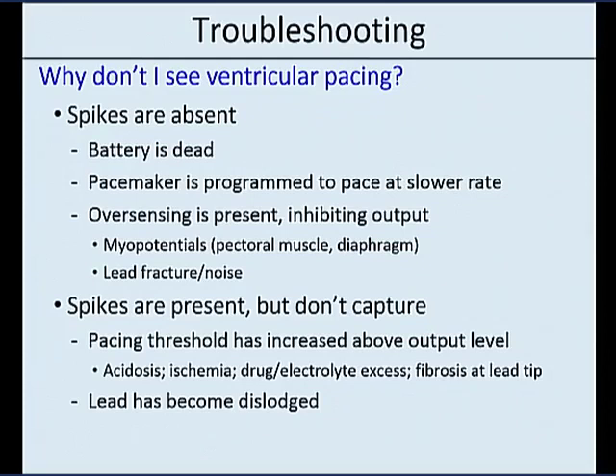Or the pacemaker is programmed to go at a slower rate than the prevailing rate. And if you say, hey, the rate's 60, why isn't this pacing? Well, maybe it's programmed to go at 50. It's not going to pace at 60. If it's programmed to pace at 70, you better see some spikes.